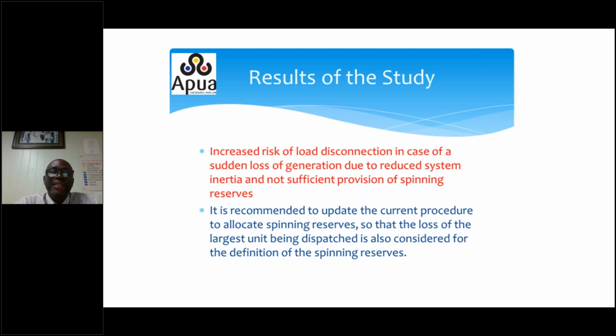Now, there's a limitation as to how much spinning reserve you can have on the grid. I mean, our biggest gen set is 17 megawatts. Ideally, you'd want to have 17 megawatts of spinning reserve, but that is not practical, and it's not the most economical way of doing business either. And another thing, you cannot guarantee that even if you have that amount of spinning reserve, when you lose a gen set, you're not going to have under frequency load shedding. Next slide, please.